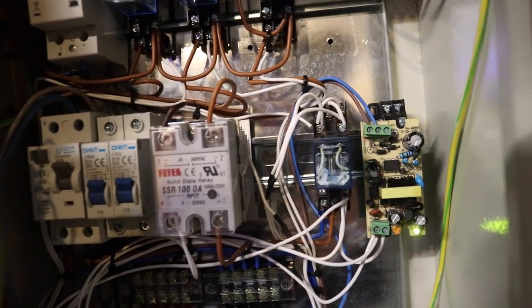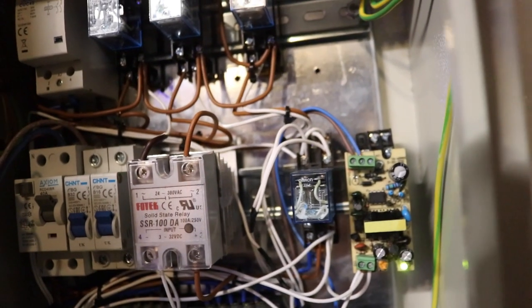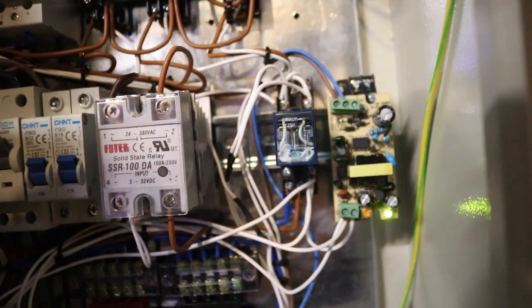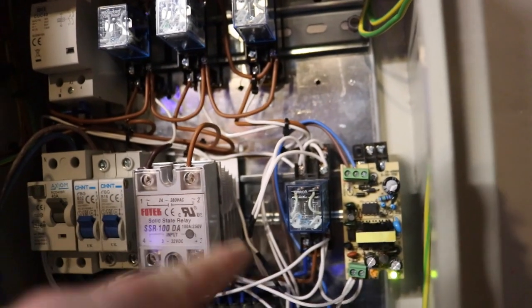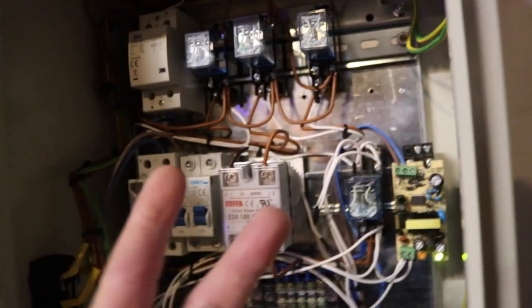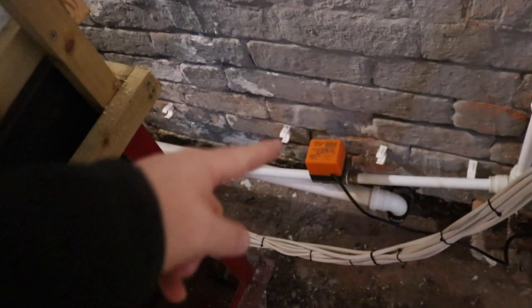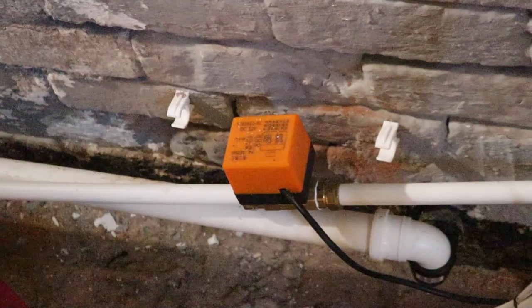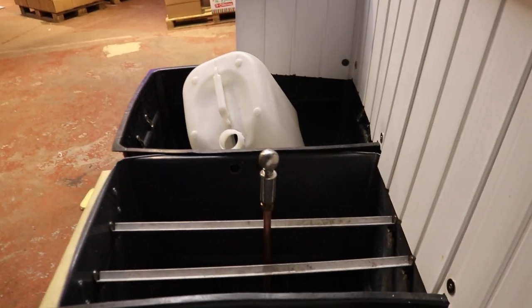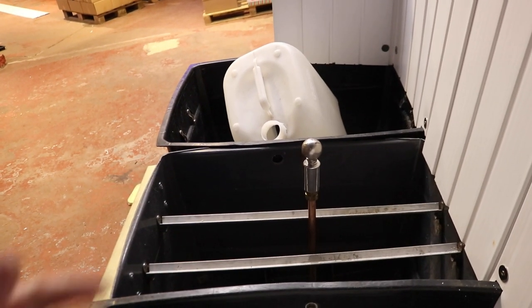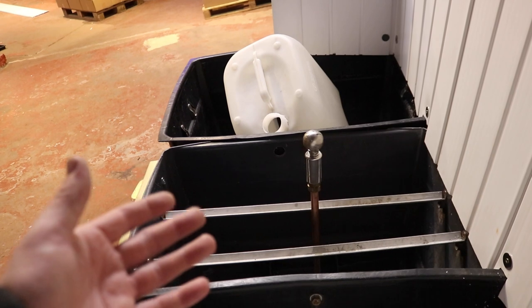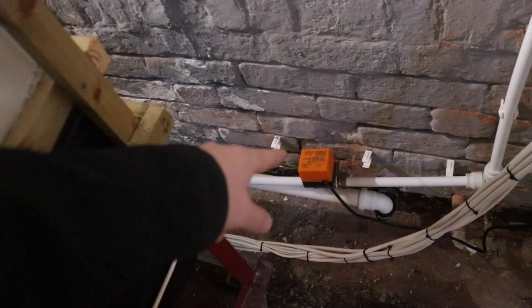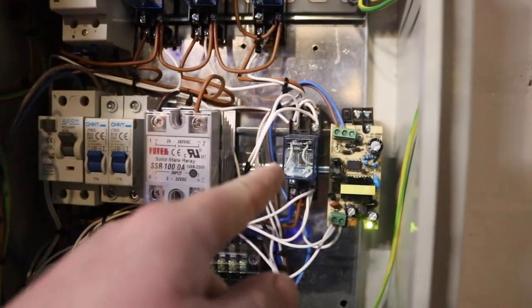Over here we've got a double pole double throw relay which has a 12 volt output. These are 12 volt relays up here, this is a 240 volt relay because we're using the pump output for the rinse pump to also switch the mechanical relay here. What that's doing is it's got a 12 volt input going through the common to the normally open normally closed contacts and it's switching the polarity of the 12 volt signal so that can operate a mechanical ball valve down there which allows liquid, allows the rinse water to come out of our IBC header tank and into the pump.